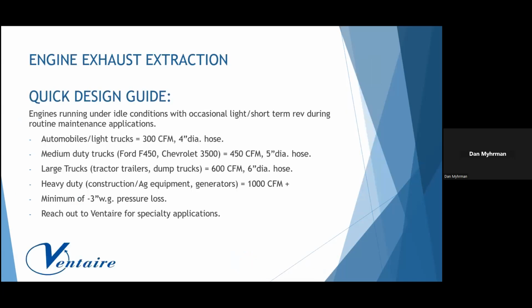It's kind of a quick design guide. Automobiles, light trucks, routine maintenance applications, pulling about 300 CFM through a 4-inch hose. Get into the larger pickups, 1 tons, the 450s, Chevy 3500s, 450 CFM through a 5-inch. Larger trucks, semis, dump trucks, 600 CFM through a 6-inch hose is typical. When you start getting into the heavy duty trucks, farm equipment, generators, minimum 1,000 CFM through an 8-inch. Anything larger than that, I recommend reaching out to Ventaire.